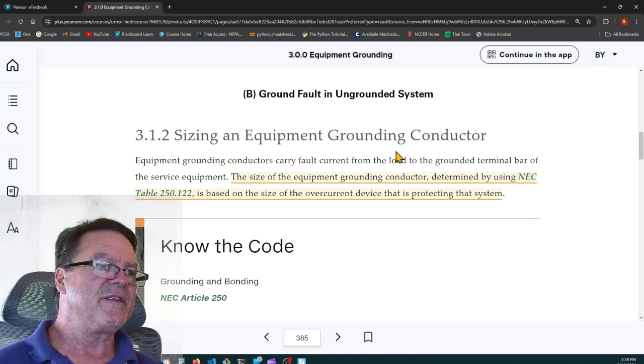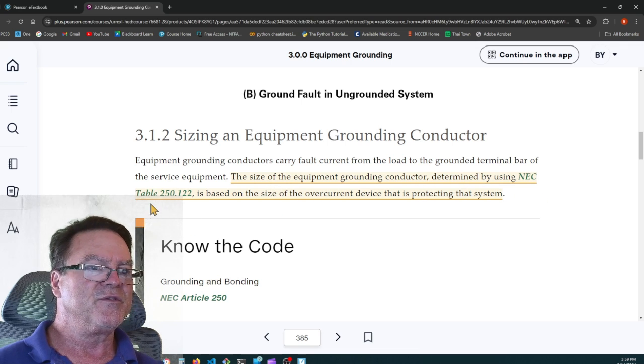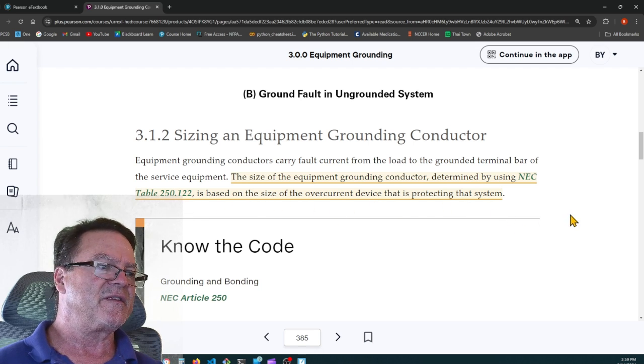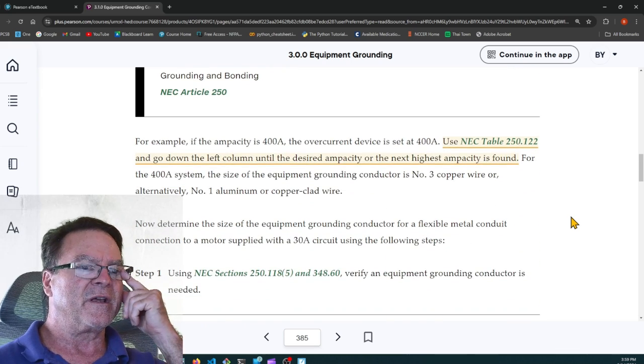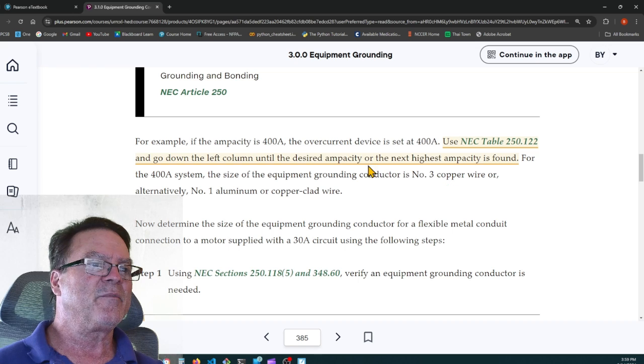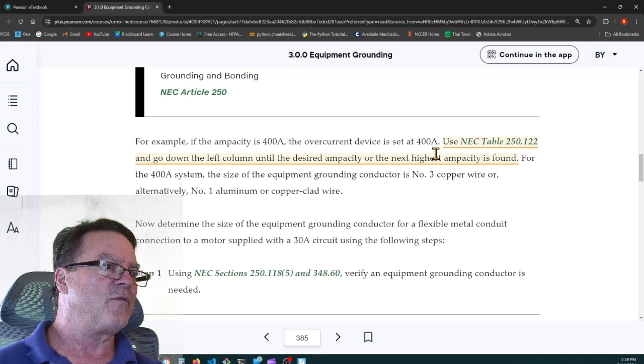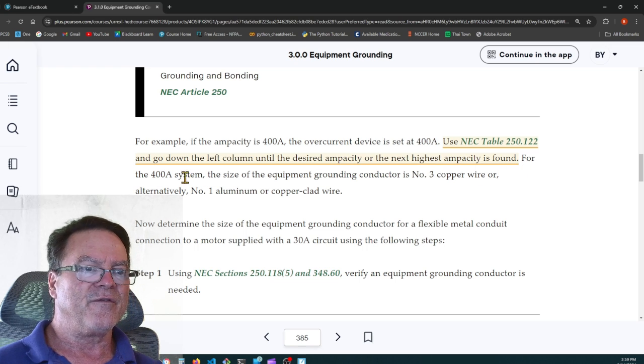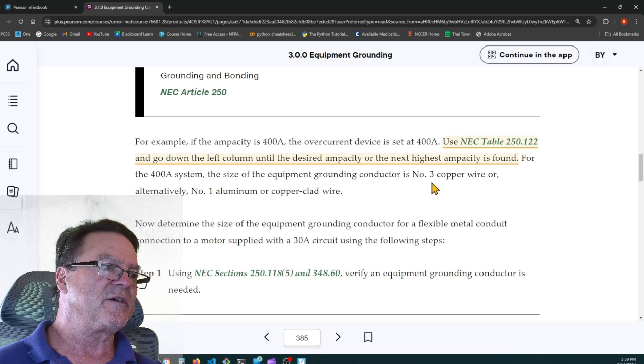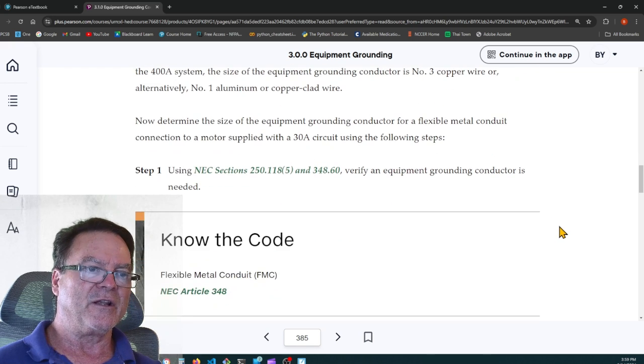Here's a highlight, sizing the equipment grounding conductor. It says the size of the equipment grounding conductor determined by using table 250.122 is based on the size of the overcurrent device that's protecting the system, not the ungrounded conductors like the grounding electrode conductor. For example, if the ampacity is 400 amps, the overcurrent device is set at 400 amps. Use NEC table 250.122 and go down the left-hand column until the desired ampacity or the next higher ampacity is found. For the 400 amp system, the size of the equipment grounding conductor is number 3 copper, or alternately a number 1 aluminum or copper-clad aluminum.